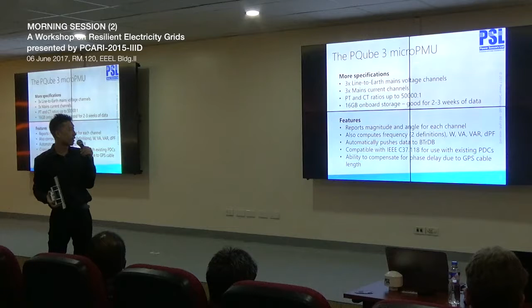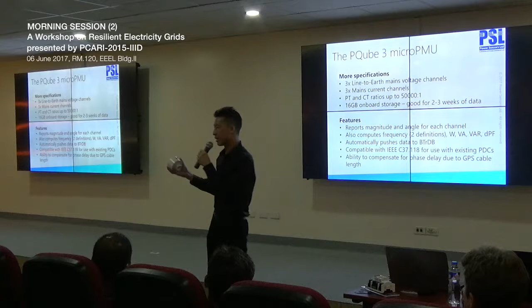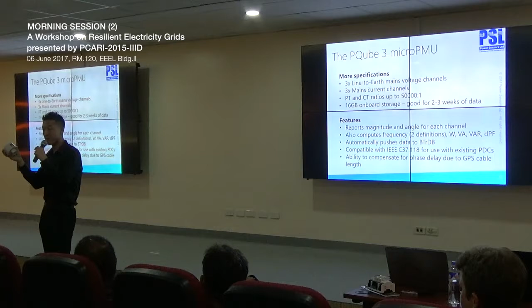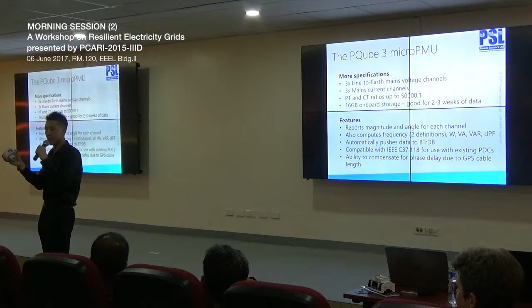And then, of course, shouldn't forget this. This is the GPS receiver. This is an integrated receiver and antenna, and we did that specifically to limit the distance between the 2 modules. By doing that, we can compensate for the delay introduced by the length of the GPS cable. Now, the speed of light is roughly 300 million meters per second, which is a very fast speed, but if you have a cable run that's 300 or 500 meters, we've actually observed noticeable delays due to the increased cable length.